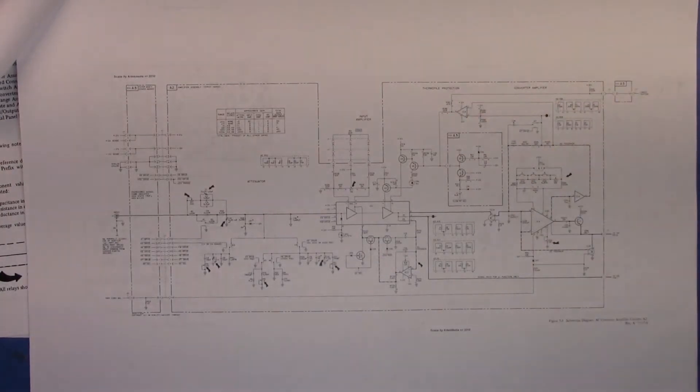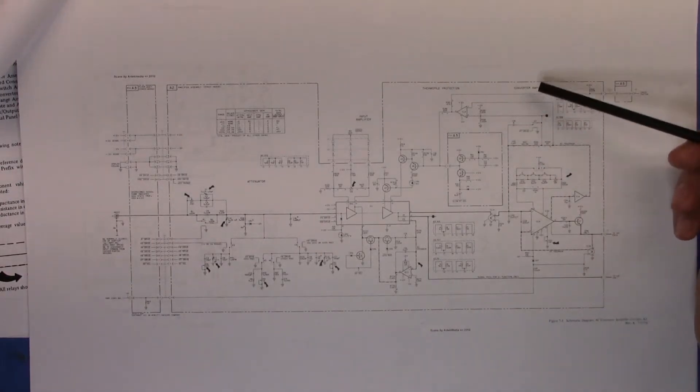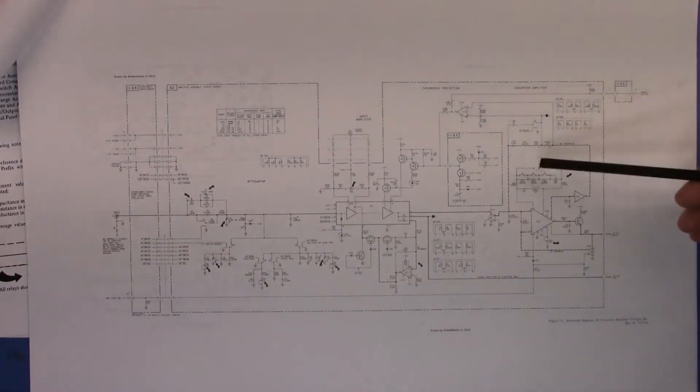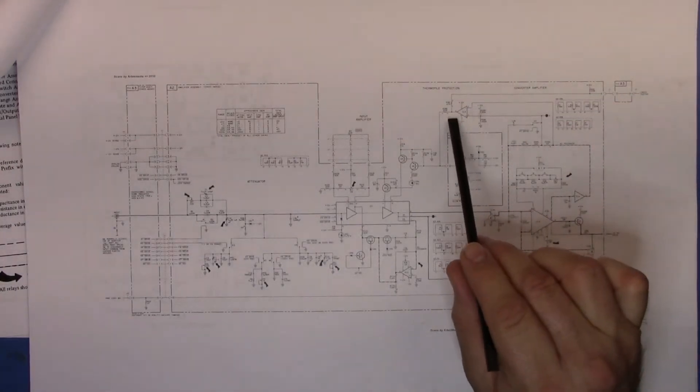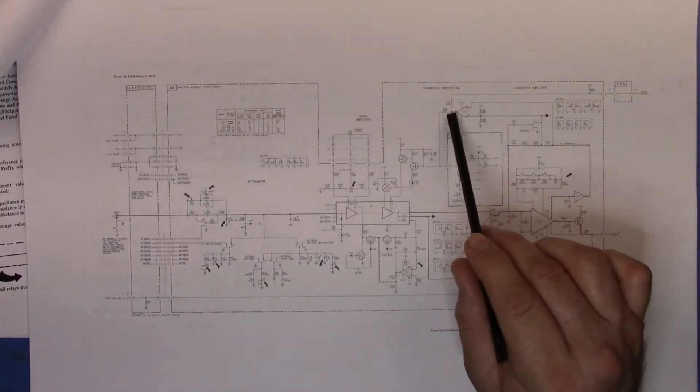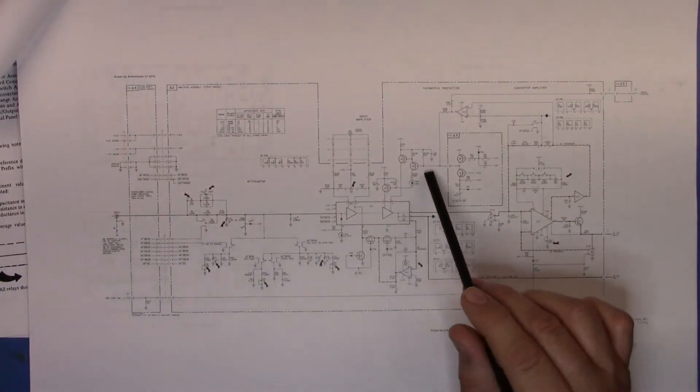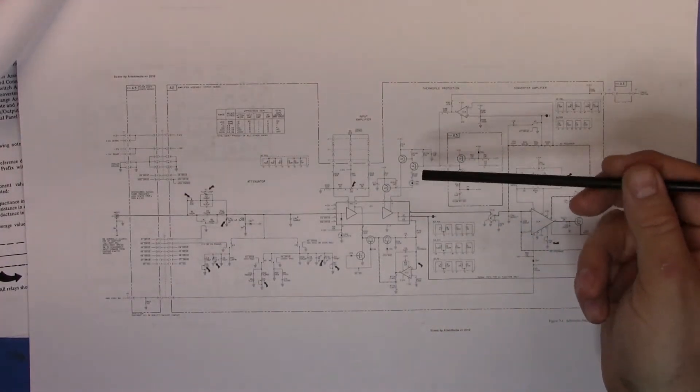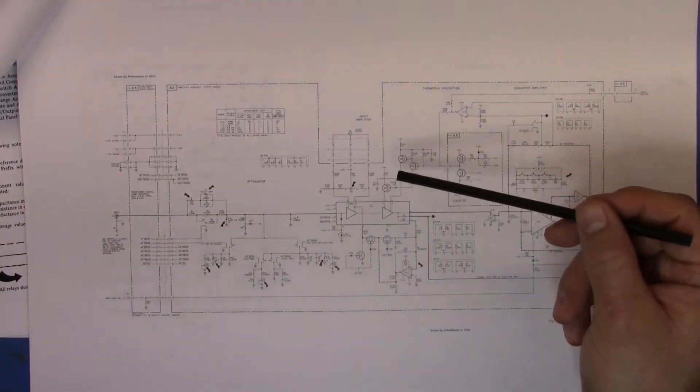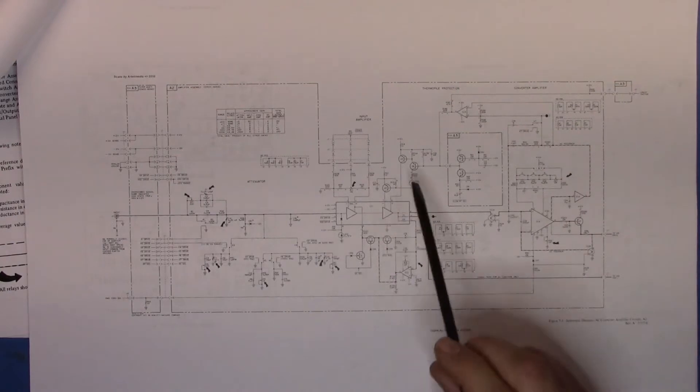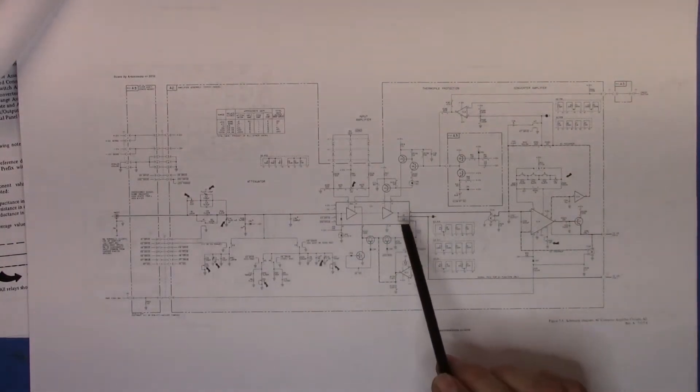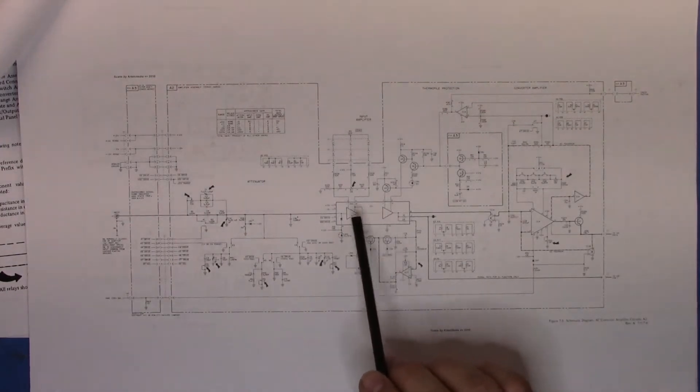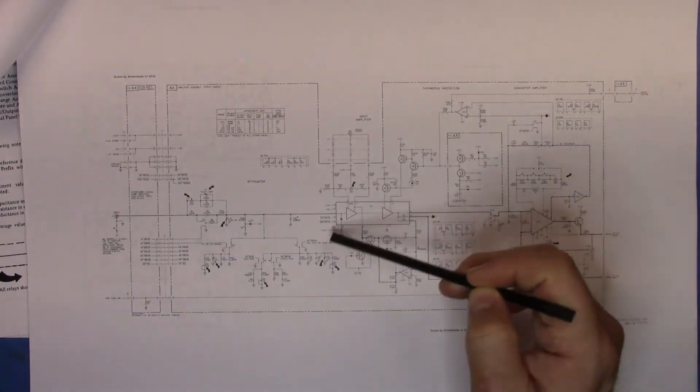It's actually used as part of the thermopile protection circuit which is up here. What it does is it basically compares these voltages versus a bias voltage here to decide what voltage is going to be put out here onto Q6. Then it's either going to turn that on or off, and if it turns that on it should turn off both of these items, which would then turn off the plus and minus rails to the input amplifier. That's how thermopile protection is supposed to work.